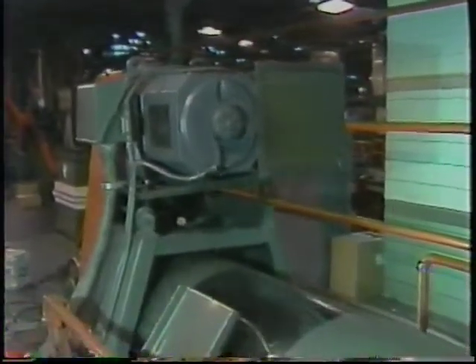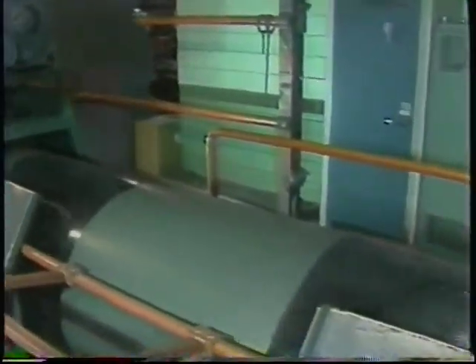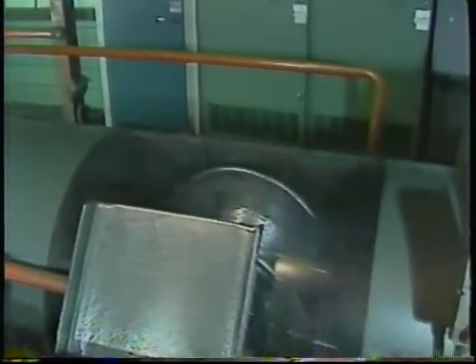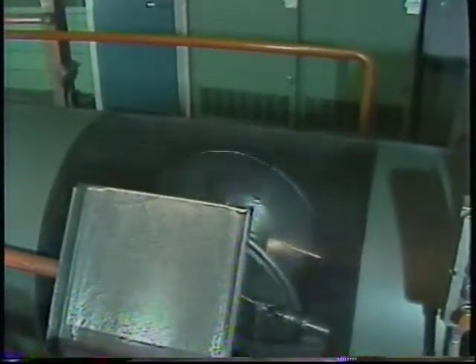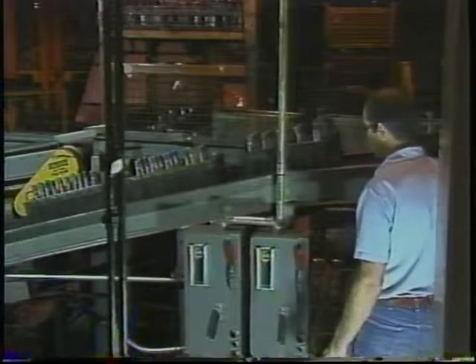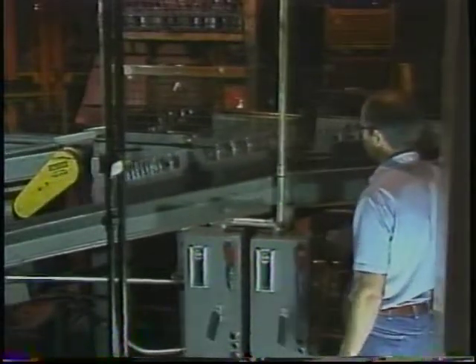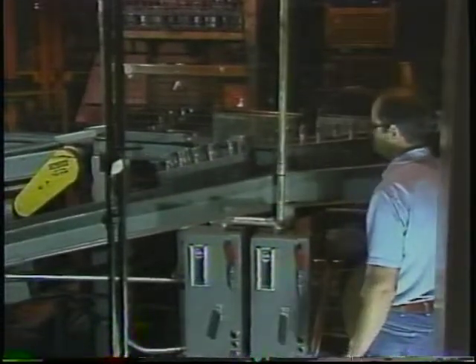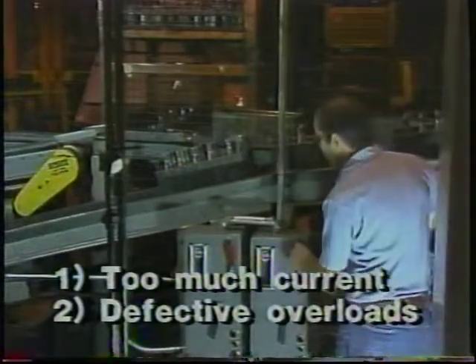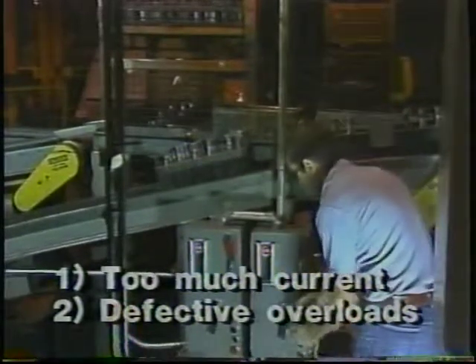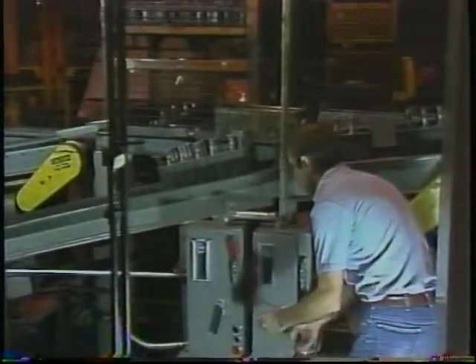Watch the motor until the OL trips again. If you hear the motor suddenly load down right before it trips, you have pretty surely eliminated the overload breaker itself. The OL is tripping because something in the load is overloading the motor. You will need to check out the equipment that the motor is driving to discover what is causing it. However, if the OL trips while the motor seems to be running normally, the cause could still be either the motor drawing too much current or a defective overload breaker. The test to eliminate one or the other of these is to measure the current to the motor.